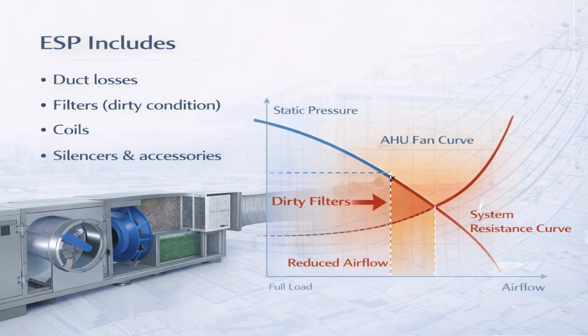When these losses are underestimated during selection, the fan simply does not have enough capability to deliver the required airflow. On paper, everything looks fine. The unit is approved, the fan is operating, but at site, the space never receives the designed air quantity. This leads to rooms that feel under-conditioned, poor air distribution, and systems that appear to be working but never actually perform. This is why realistic static pressure calculations and allowing for dirty filter conditions are critical to reliable HVAC performance.